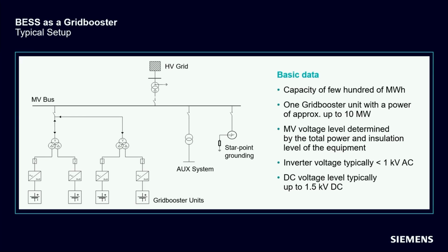On the medium voltage level, we typically have some auxiliary transformers which are used to supply auxiliary loads like air conditioning, heating, lights, etc. Furthermore, depending on the star-point earthing method, the medium voltage system can be equipped with a star-point grounding transformer, which helps to detect and clear single phase-to-ground faults in the medium voltage system, such as cable or busbar faults. The total capacity of a grid booster is a few hundred megawatt hours.